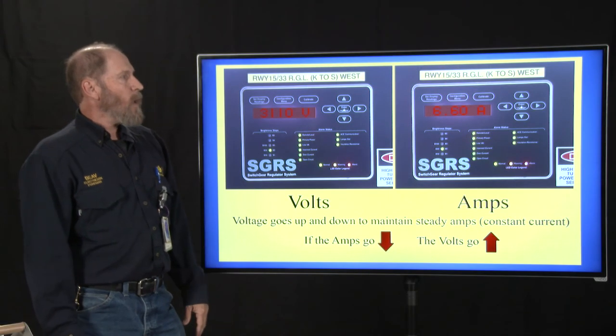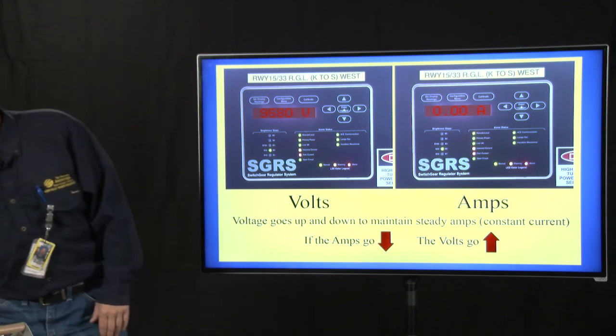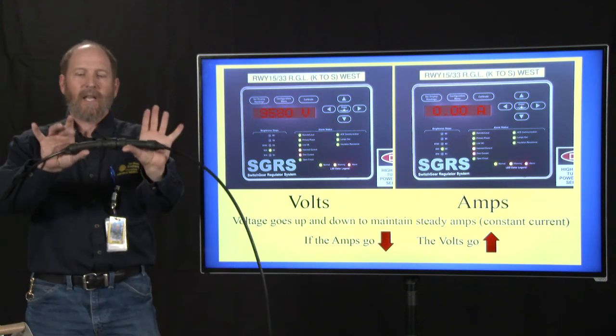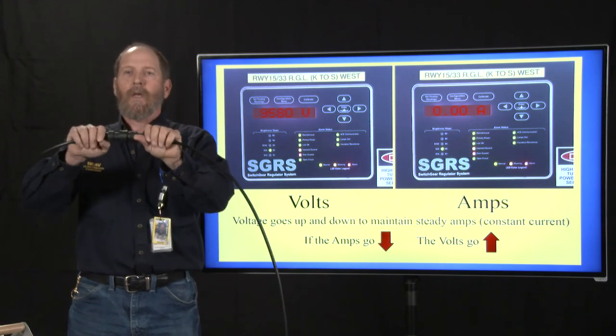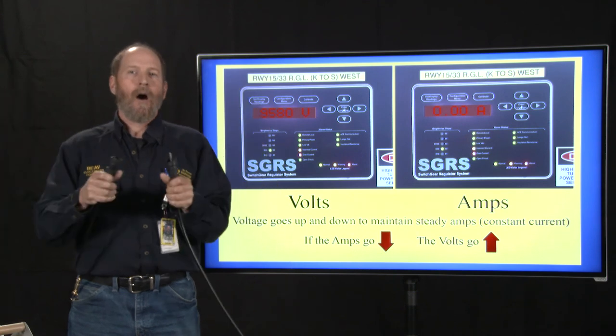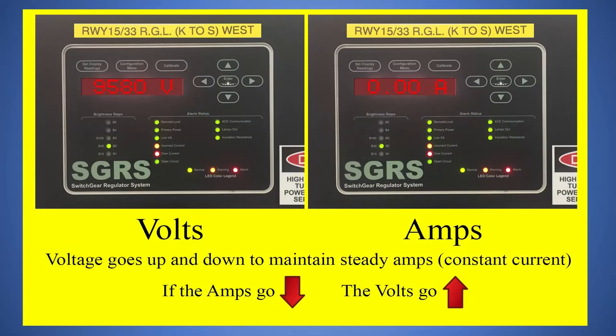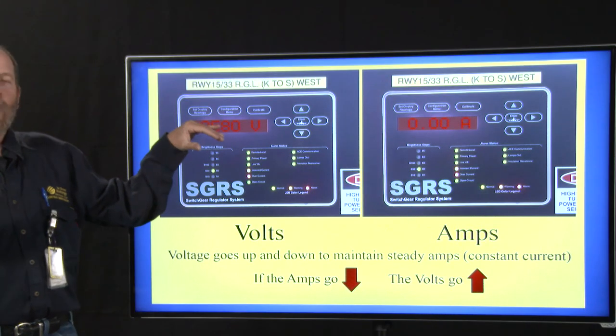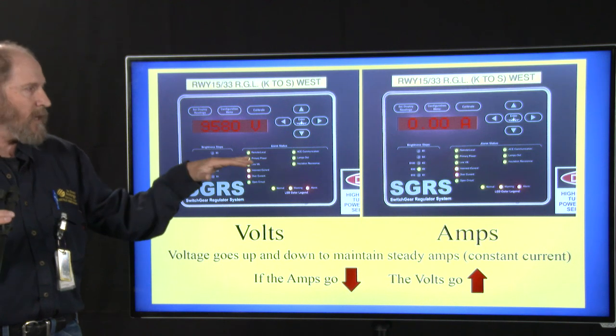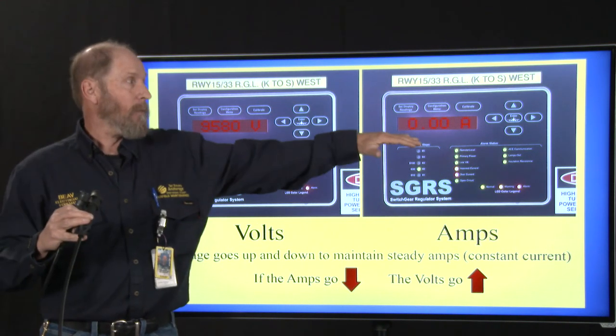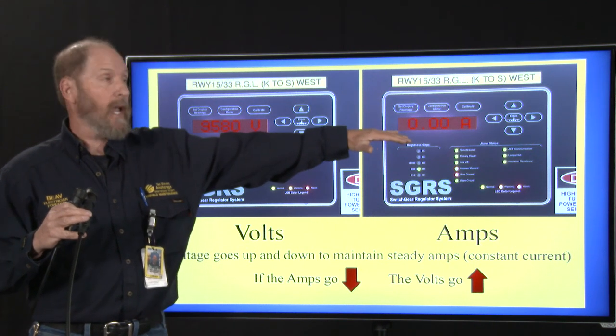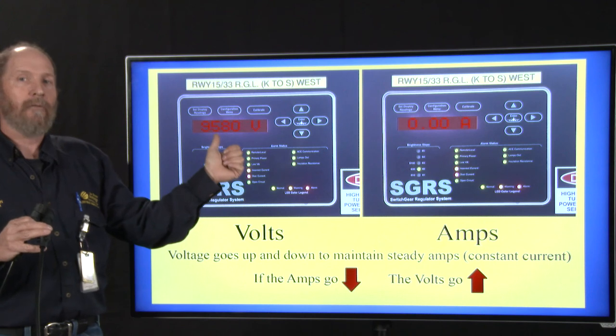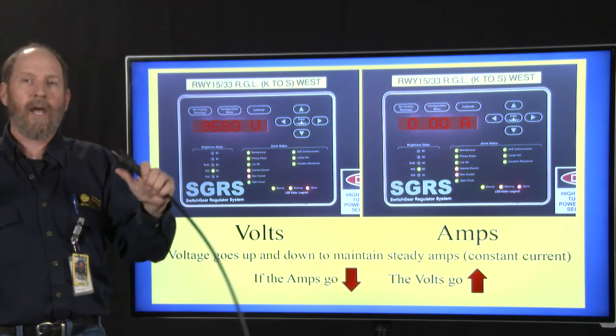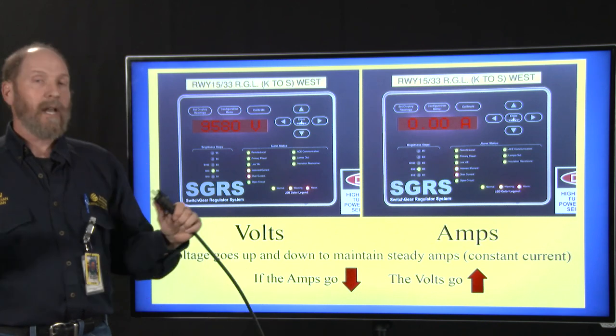Okay, so what happens if we were to take a live constant current connector and pop it open? Our amps are going to drop down to zero. Our volts are going to go right through the roof. This regulator is going to say, I've got to get these amps up. This is my job to maintain 6.6 amps in here, and I'm going to give it everything I have, all the volts I can put out, in order to try to make those amps flow through this wire. And it will. It'll put out between 9 and 10,000 volts, and it will jump a blue arc 2 to 3 feet between these connectors.